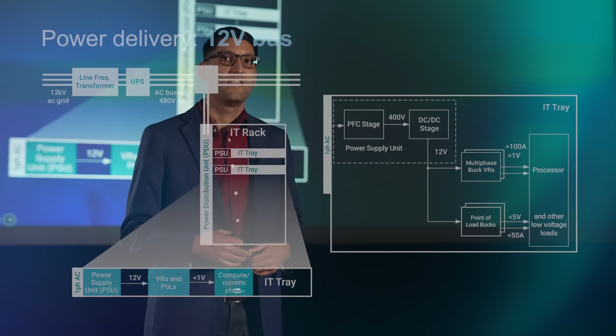Now, the PSU has two stages. There's a power factor correction stage, followed by an isolated DC-DC stage with typically a 12-volt output. Finally, there's a multi-phase buck voltage regulator and point-of-load buck converters that convert power to the low-voltage supply rails of the processor and other low-voltage loads. This architecture is seen when you have relatively low power loads, maybe processors in the hundreds of watts range, and the PSUs probably are rated for maybe a few kilowatts, and the total rack power might be in the low tens of kilowatts. And this is what you'd see historically in your generic computing and storage server applications.